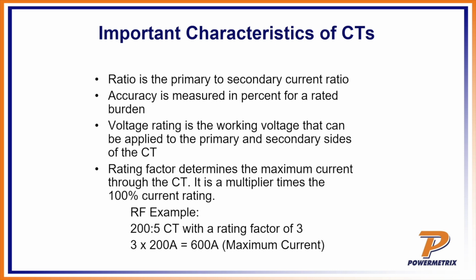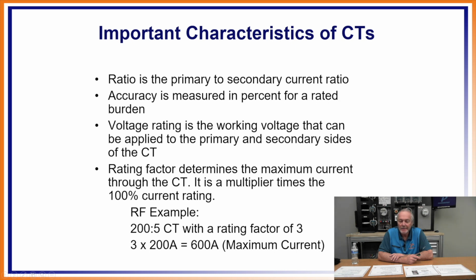So these are some of the things we just showed on the nameplate. The characteristics of the CT. Ratio, the primary to the secondary ratio, like we said, 100-to-5. The accuracy is measured in percent for a rated burden. But you saw that a minute ago, it said at 0.1, right? The accuracy is measured as a percent for a rated burden, because what are the two things that affect the CTs in a bad way? Burden, too much burden, and temperature, right? So those are definitely going to affect the ratings, and the nameplate stuff that we see on that CT is going to be burden and temperature. And you'll see that here in a second.